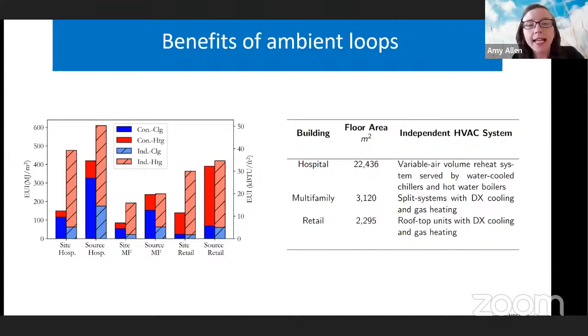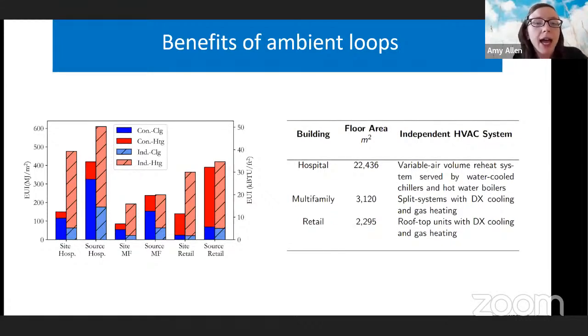I considered one case study district consisting of 5 prototypical buildings based on the US DOE prototype building models, and considering those with their independent systems, which are shown in this table at right, and also in a case in which I modified the building level HVAC systems to be compatible with an ambient loop. That is, to use water source heat pumps tied to a moderate water temperature source for space conditioning. And I considered an ambient loop operating in the two-pipe configuration similar to the ones shown on an earlier slide.